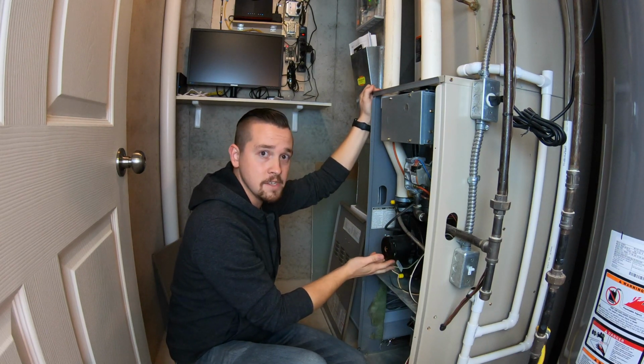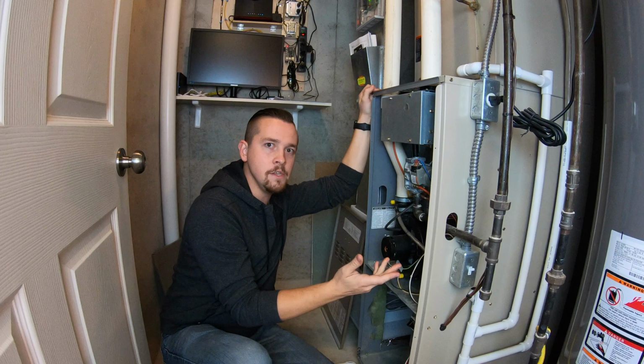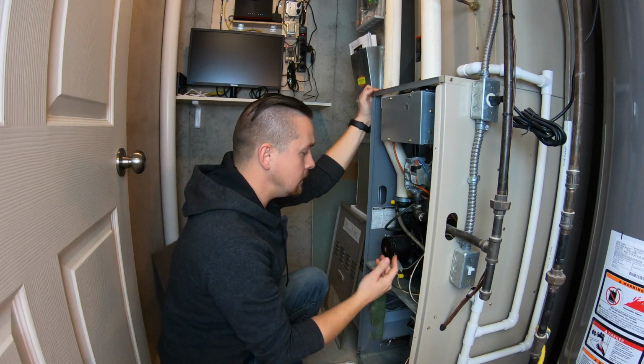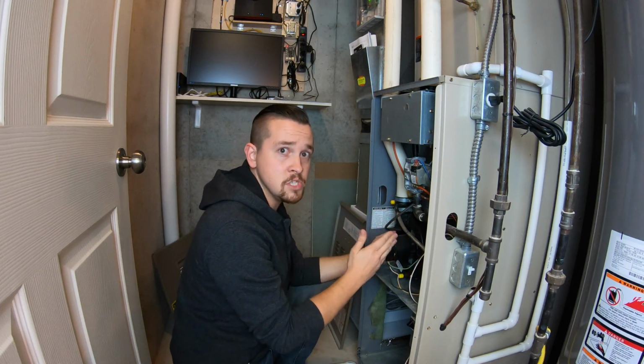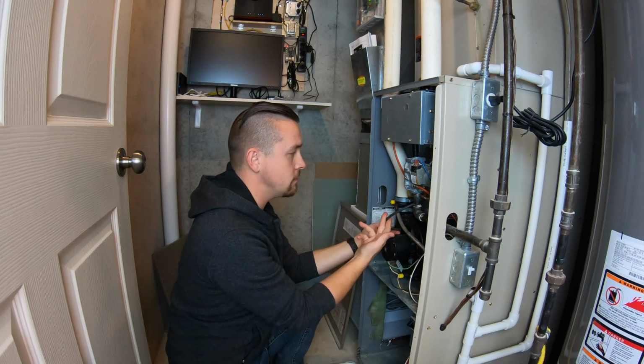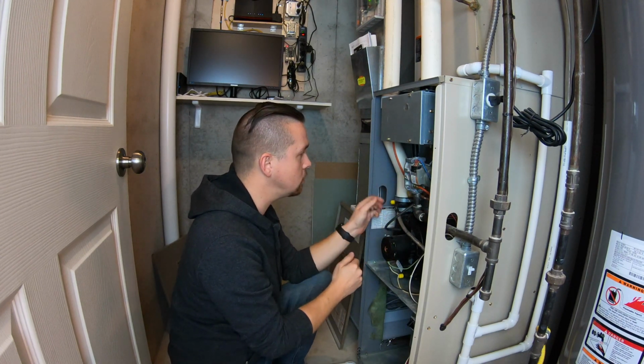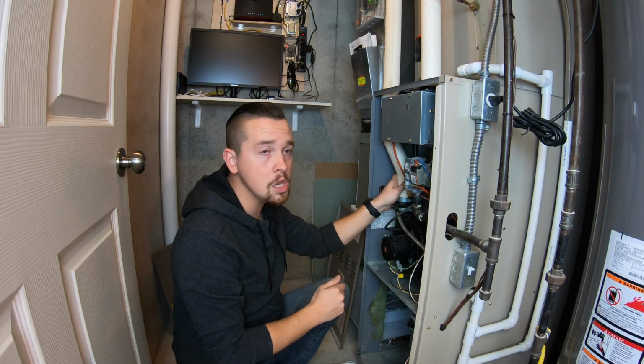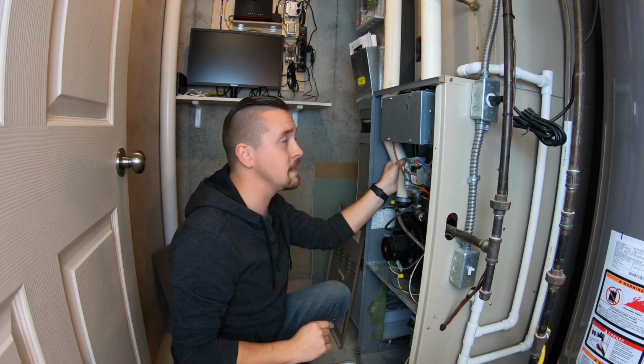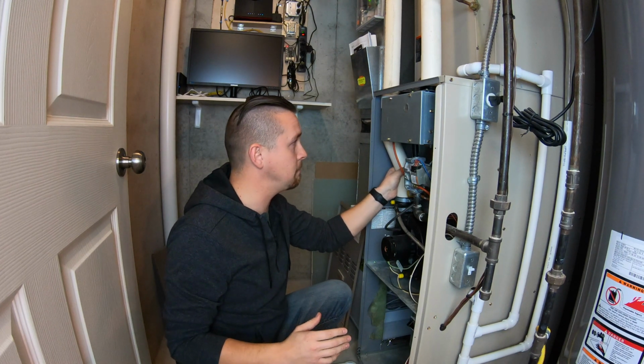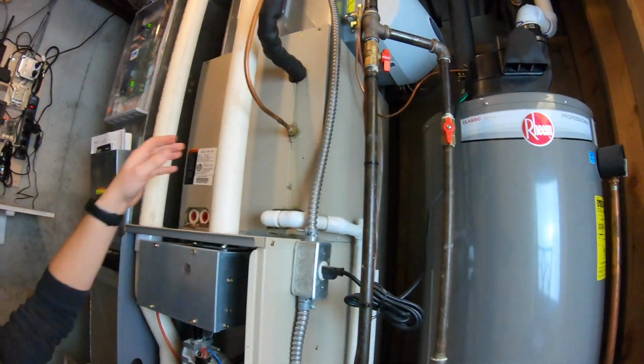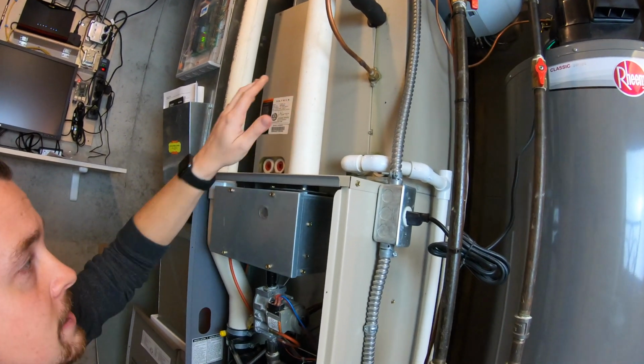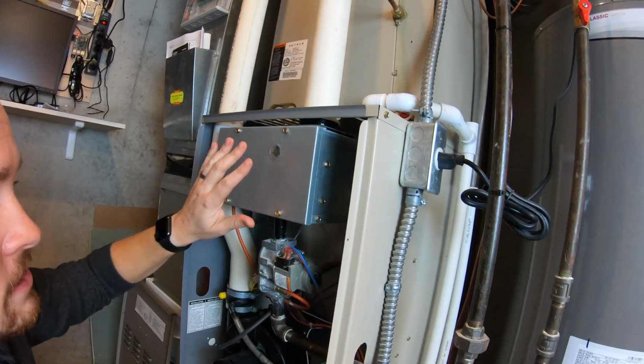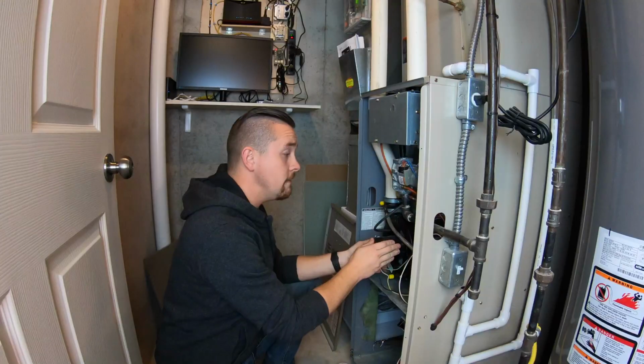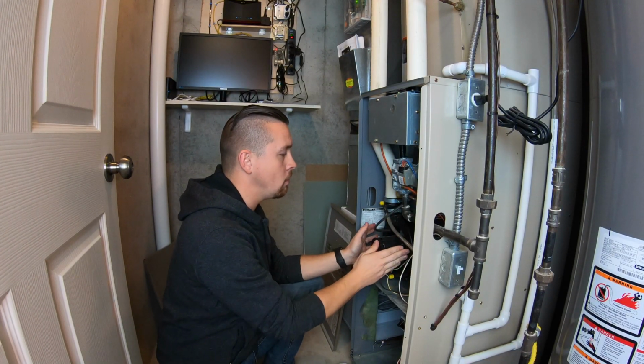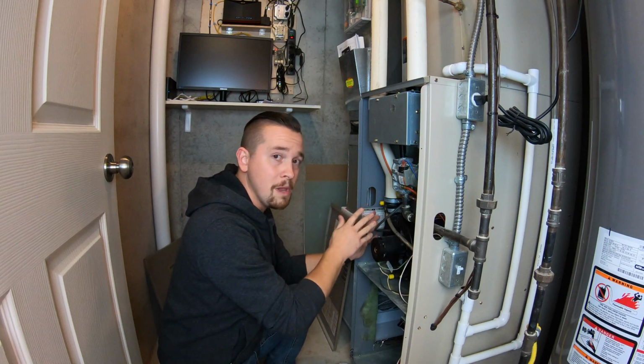If this is hot to the touch and it's not moving, then you know that there's a problem. Additionally, this could be running and spinning and doing just fine, but you don't have the pressure that you need to close that pressure switch. You might have a bird or a squirrel inside of this pipe here. Sometimes like big nests and things can end up in this pipe. Additionally, the intake pipe here could be clogged and not allowing enough air to flow through the heat exchanger to close that pressure switch. If this motor isn't working, I always recommend pulling it off of the furnace to make sure that there's no blockage in there.